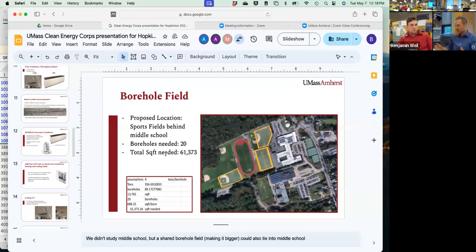You've got good windows, you've got decent insulation. And we know the actual performance. That regression basically says that's what your envelope is like, plus your ventilation. So everything that we've sized, when you add the ERVs, about 1/3 of your energy use is for ventilation air, roughly. So the ERVs are going to take that third and in the winter cut about 75% of that off. And in the summer, it's more like about 50%, because of humidity and their maximum capacity for moisture recovery is about 50%. So they help. They don't really impact the envelope.